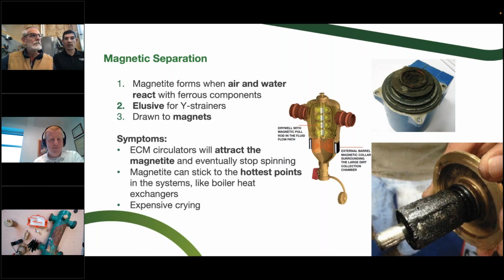At Caleffi North America in Milwaukee, we had a couple of pumps fail and we took apart the circulators. We found this on the rotors, and it's like, this building is less than 20 years old. Why do we have this stuff? This isn't a 100-year-old hotel with a bunch of cast iron radiators, but there was just enough magnetic garbage floating around in that building that some magnetic debris caught on the circulator, and then the pump started behaving poorly because it couldn't spin freely. The water is cooling these ECM pumps with a big magnet right in the center of everything.